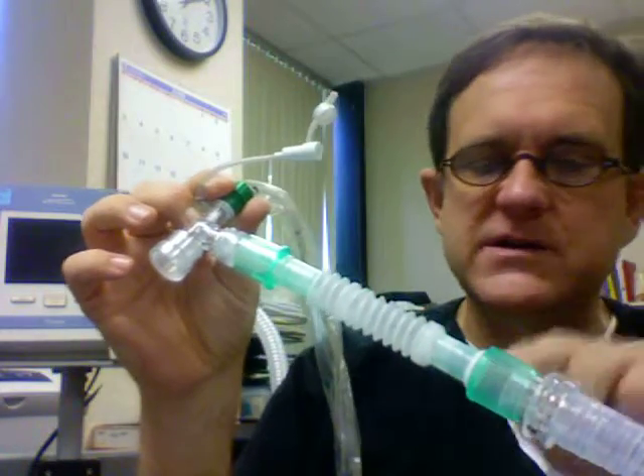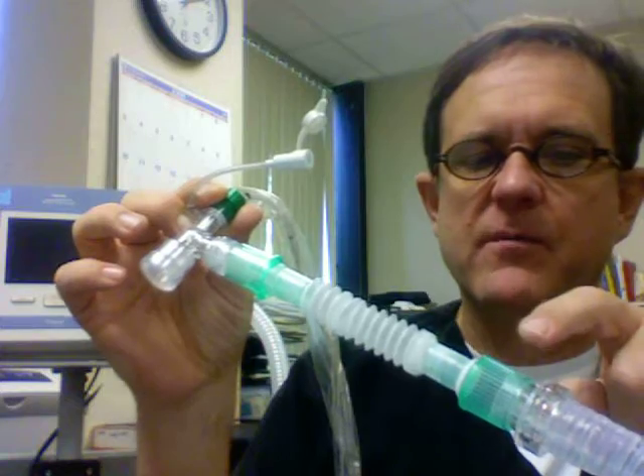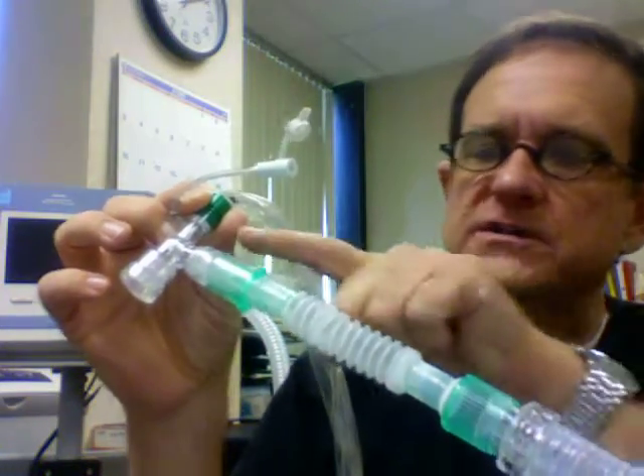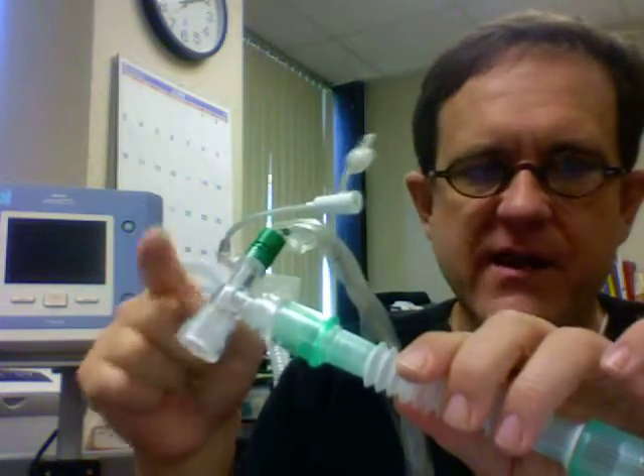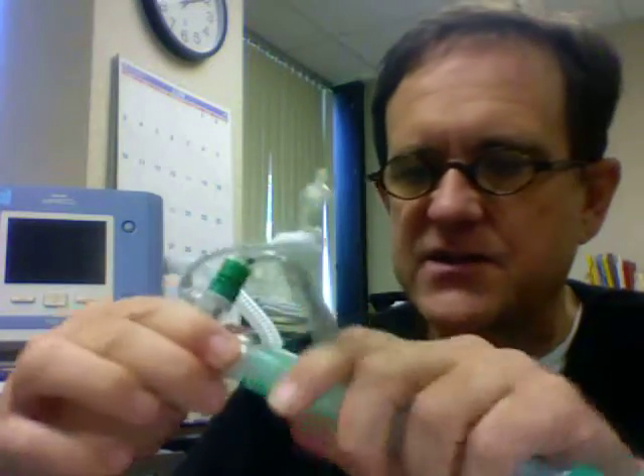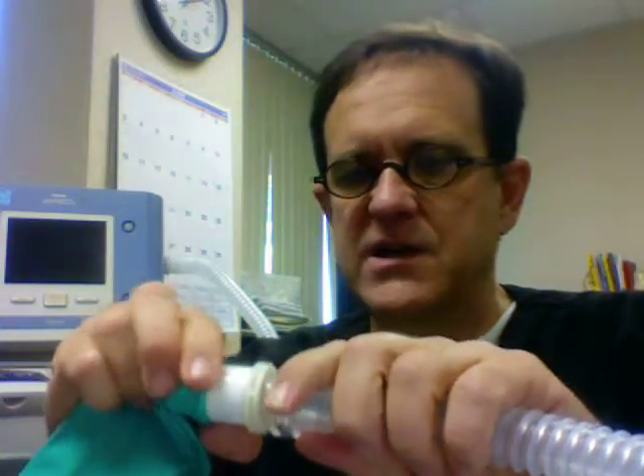Now, you see the Whisper 2, one end is connected to the machine, the other end I have the Whisper 2 swivel, and for my adult patient, say for example if I were going to hook a tracheostomy to it, I could put this device on. It's an accordion type piece that makes the transition from the 22mm circuit side to the patient's airway side, and I have the ballard on here. I'm going to take this off, and in the place of this I'm going to put my test lung so we can see it operate.